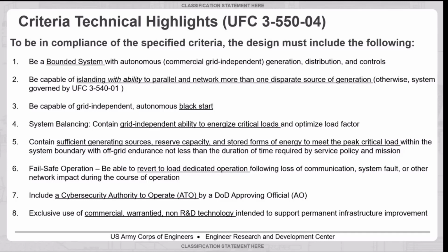It has to be able to operate by itself, and we have to be able to say here's the boundary of the microgrid. It has to be capable of islanding, with the ability to parallel and network more than one generation source. It does not necessarily have to contain more than one generation source, but it must be able to integrate at least two. It has to be capable of grid autonomous black start, so if you can't start from a dark condition, you're not a microgrid. It has to do system balancing, maintaining generation and load balance within its boundaries.